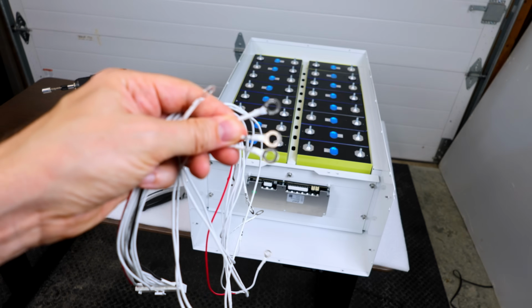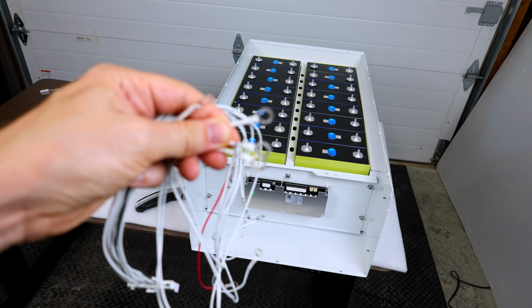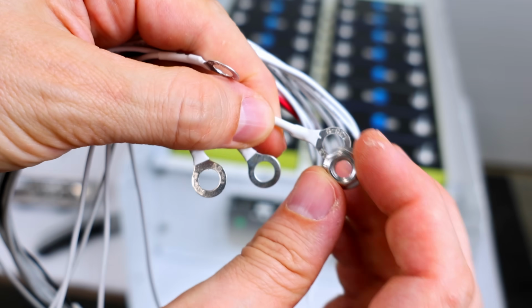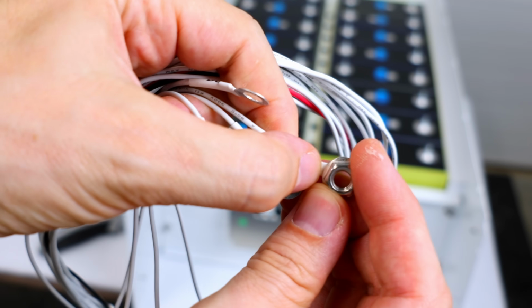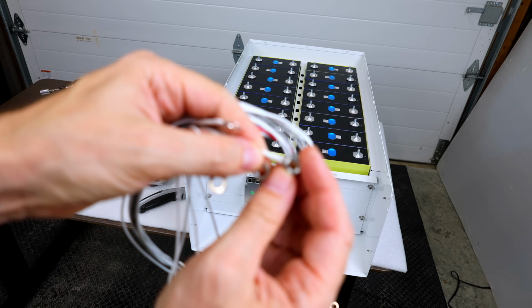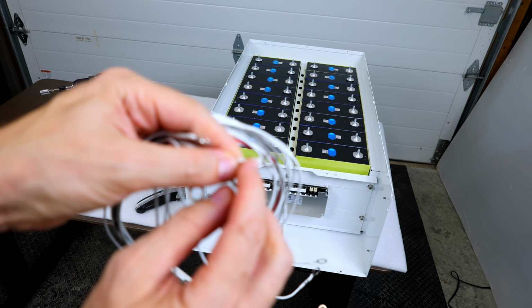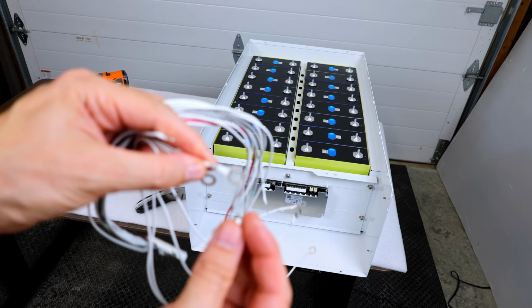Most of the balance leads are okay, but there's a couple of them where the insulation is just a little too far up on the eyelet there. A good way to check is to just put the nut over it, and if the nut is covering the insulation, then you know it needs to be trimmed back a little bit. So I'll go ahead and fix that, I want to make sure that there's no insulation in my joints.